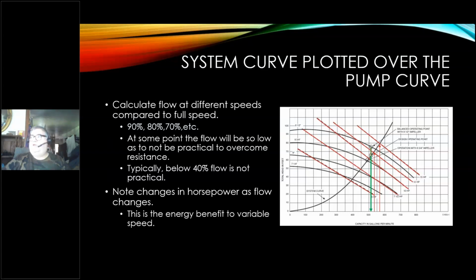This is where we really got to use this. You won't know this unless you go out there and measure it, or look at the pump curve and say, okay, what's my safe operating point? How high can I go with this thing without getting into trouble? Unless you do the measurements, this is your only other tool to say, hey, I'm okay, or hey, I need to get a bigger motor. Other than touching the motor and burning your hand. I mean, that also is a good check.